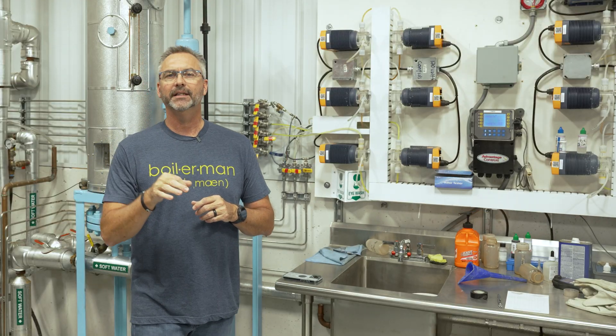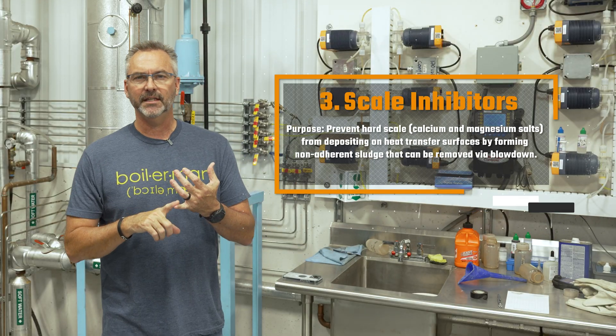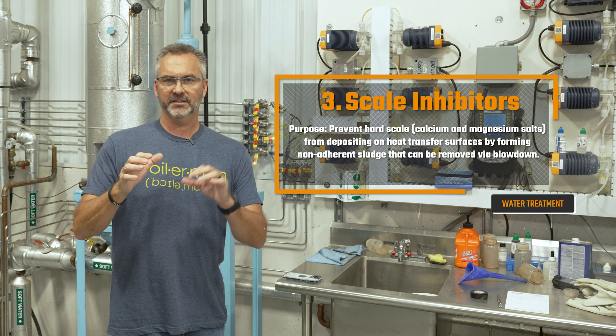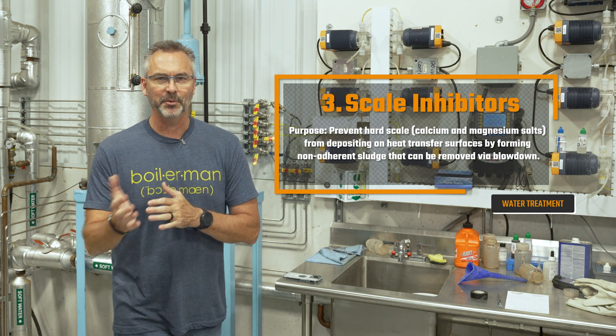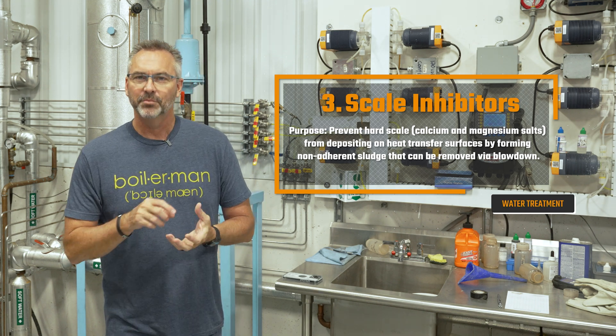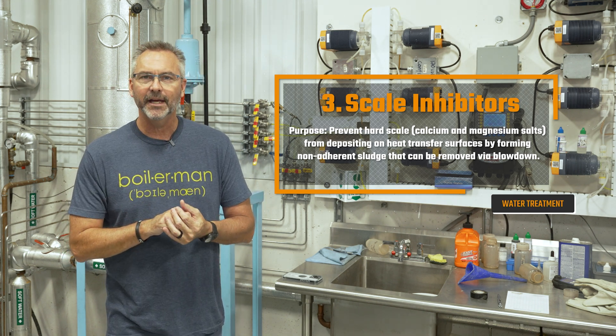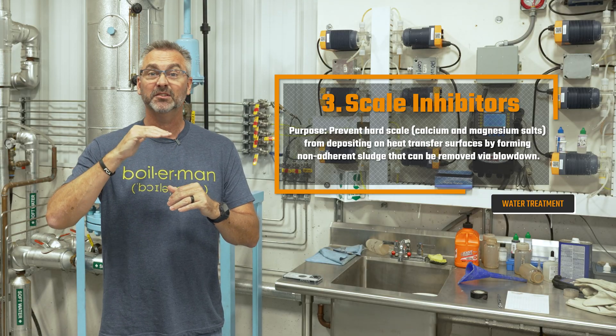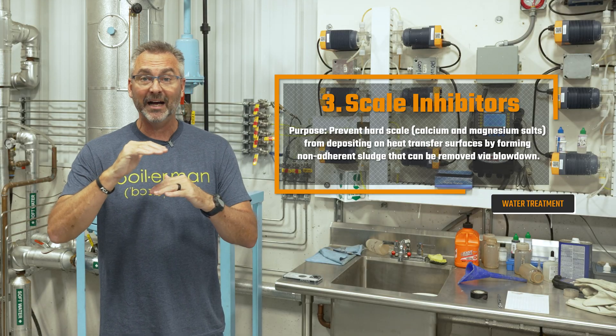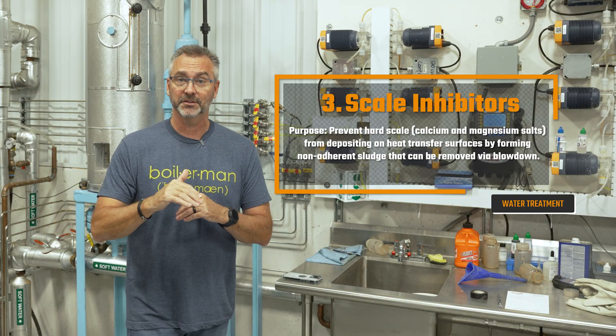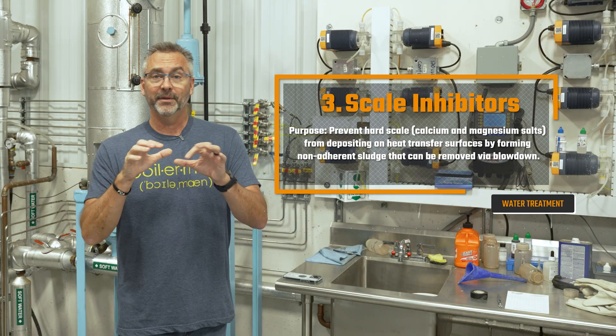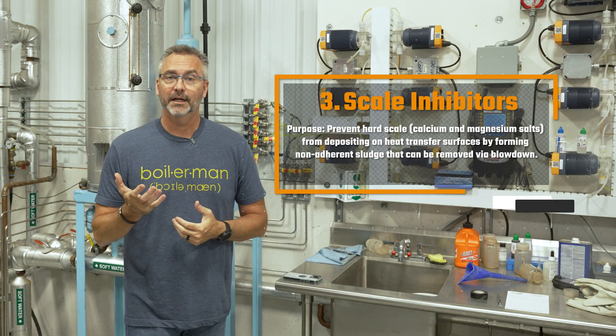Number three is scale inhibitors — phosphate treatment. The purpose is to prevent hard scale. Calcium and magnesium salts deposit on heat transfer surfaces, and phosphate treatment addresses this by forming non-adherent sludge that can be removed via blowdown.